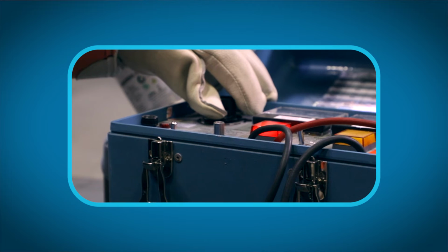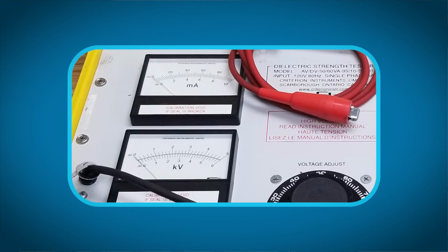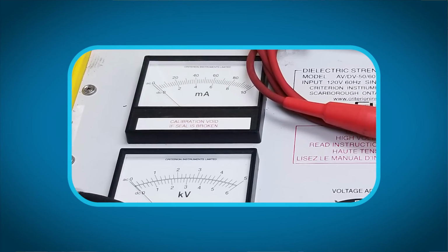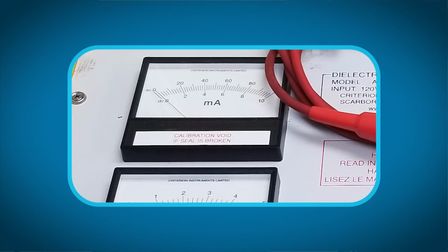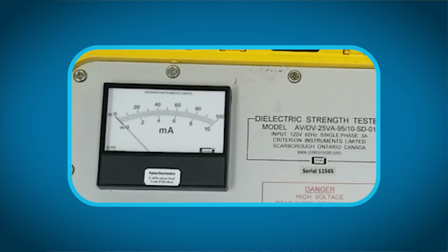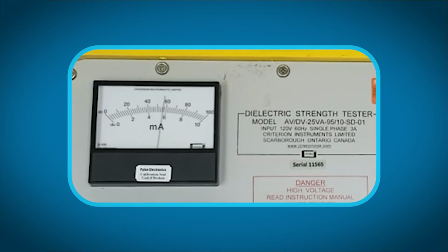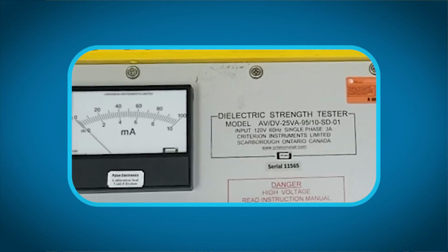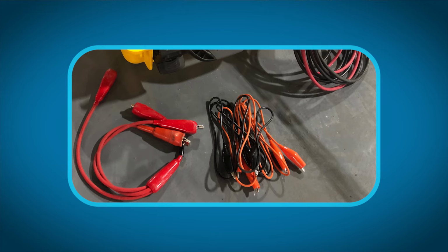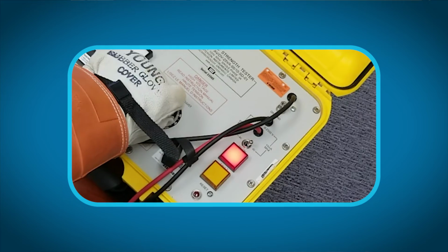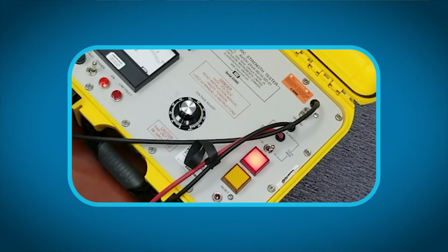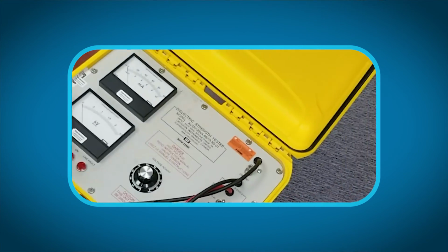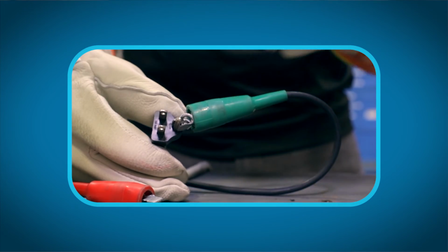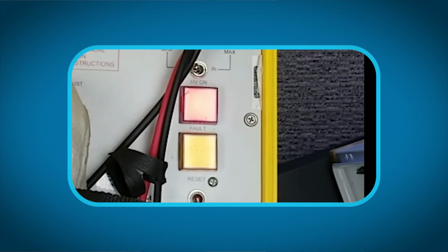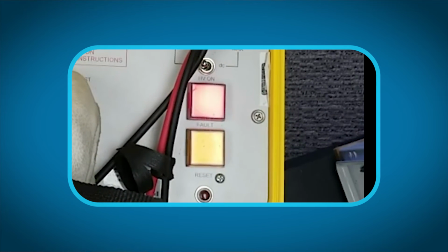Turn the voltage knob clockwise until a breakdown indication between 90 and 100 mA AC or 9 and 10 milliamps DC. This verifies that the setup works properly. If additional leads are used in the setup, they must also be verified individually or in series in the same manner. Turn the voltage knob back to 0 and switch the tester off. Disconnect test leads from each other. If the meter does not trip off, the equipment will require investigation and possibly servicing.